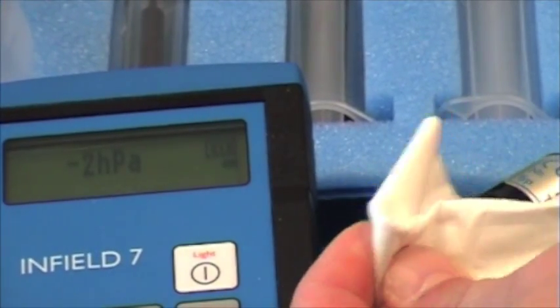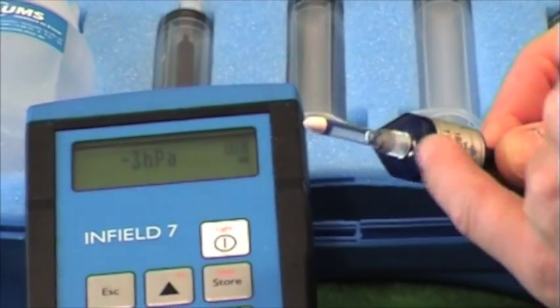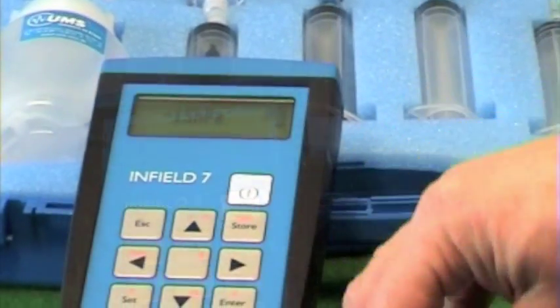Use a dry towel and shake the T5. Now the value should rise up to 800 hectopascals or higher. If not, you may see a bubble and the T5 needs refilling.